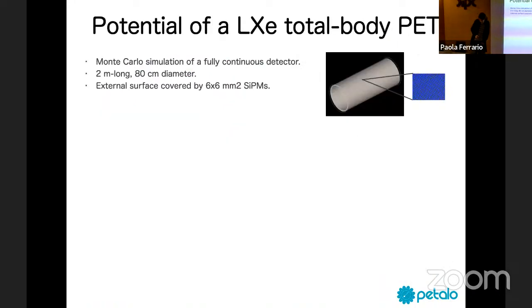So the first step that we took was to try to demonstrate the feasibility and the performance of a full body, total body PET scanner with this technology. We did that with a Monte Carlo simulation of a fully continuous detector. You can see here, it's basically a cylinder, hollow, so it has a hole in the middle. And there are silicon PMs all over the external surface, pointing towards the internal part of the cylinder. We used 6 by 6 millimeter silicon PMs, which is a good compromise between not having too many of them, which is complicated, and having a good granularity to determine the position.